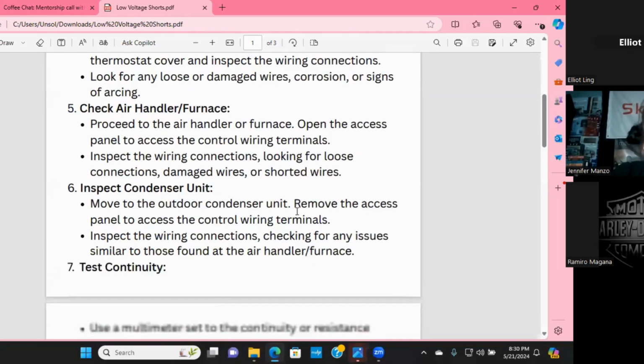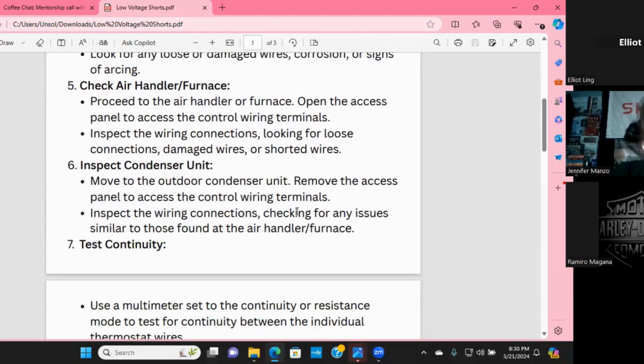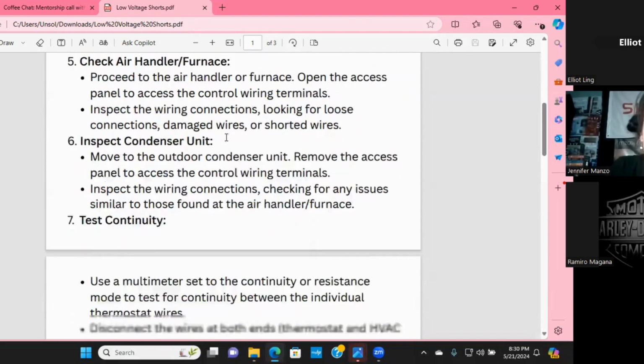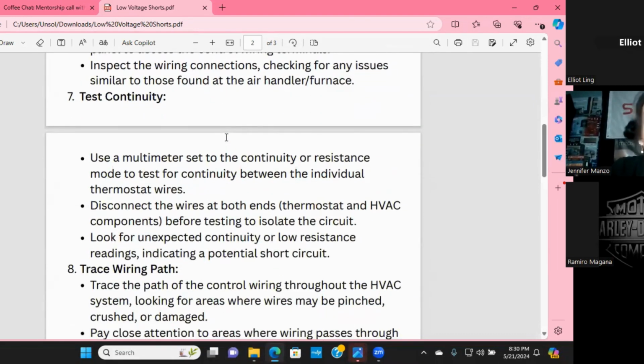And then check your air handler or furnace wiring. I always check the indoor unit first, guys. It does not matter. You can check whatever unit you want. You're going to do the exact same thing, doing the tug test, checking for burnt, loose, or chewed wires in every spot. You're going to check the condenser, the air handler, any spot you see wiring, you're going to check it when it comes to that 24 volt.